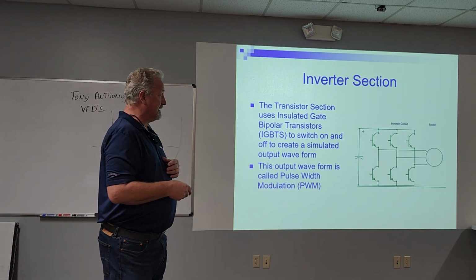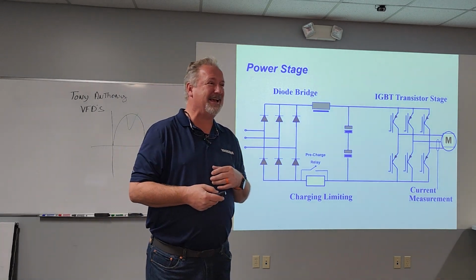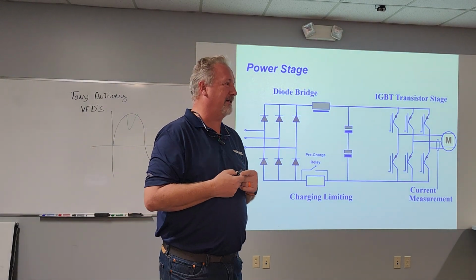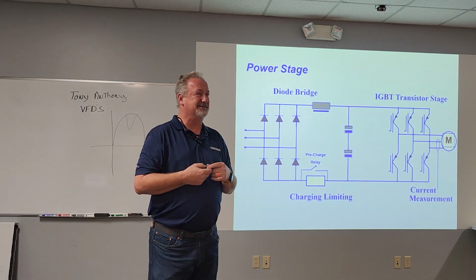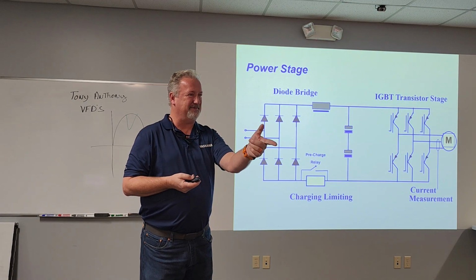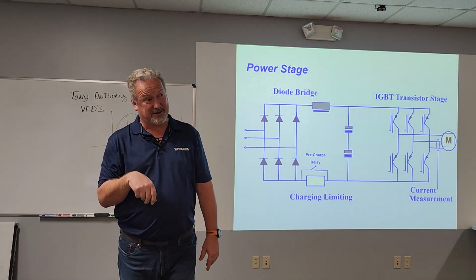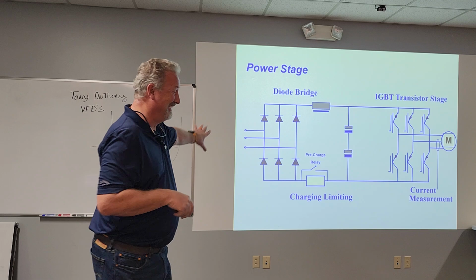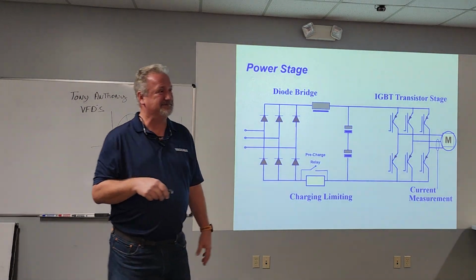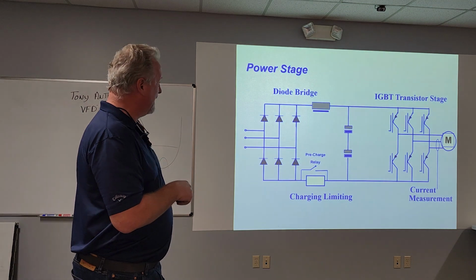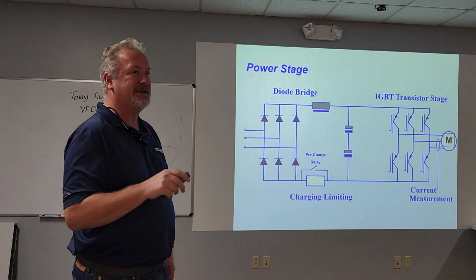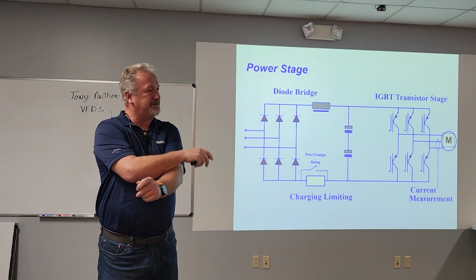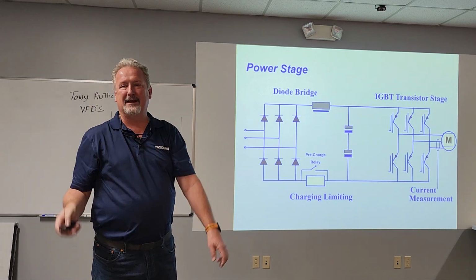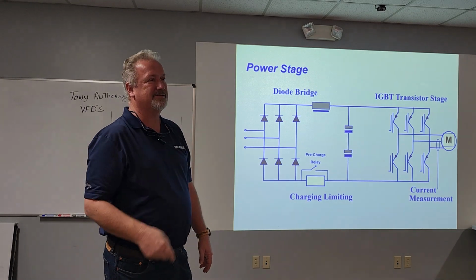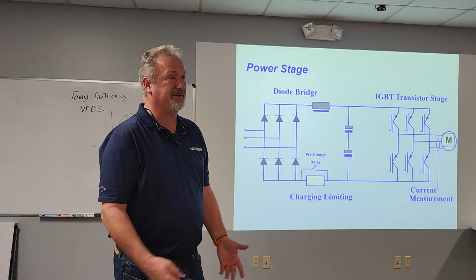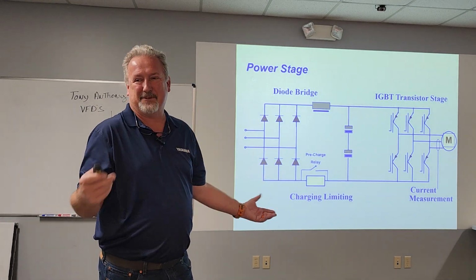So since it's a fancy diode, guess how you check the output section of a drive if you think you got a problem in your IGBT section? We did the input side. You take the diode checker. This time you take the motor leads off. You also de-energize the drive, by the way. You take the motor leads off, and you do the same thing, except now instead of doing L1, L2, L3, you're going for the plus to minus to T1, T2, T3. And you're checking it both ways on all three phases, plus and minus. That's how you can check the output section of a drive to see if you got a problem with your IGBTs. You think about this fancy drive, to truly check the input and the output, all you need is a diode checker.